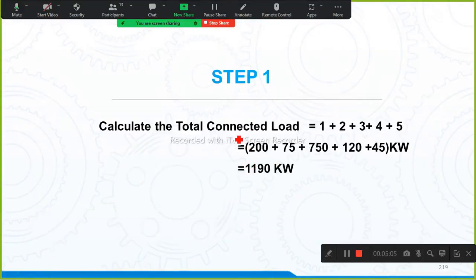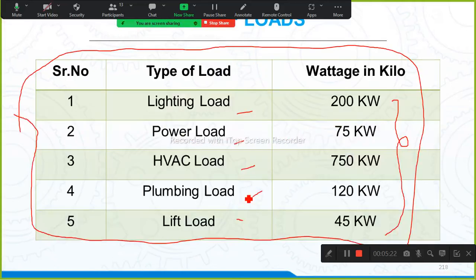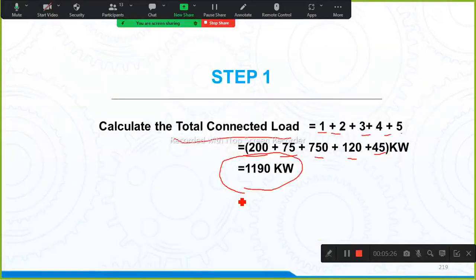Now adding up that total, step 1, calculate the total connected load, that is equal to 1 plus 2 plus 3 plus 4 plus 5. That is 200 plus 75 plus 750 plus 120 plus 45. Adding up the total, we got 1190 kilowatt as the total load. Step 1, adding up the total load: 1190 kilowatt is the total load.